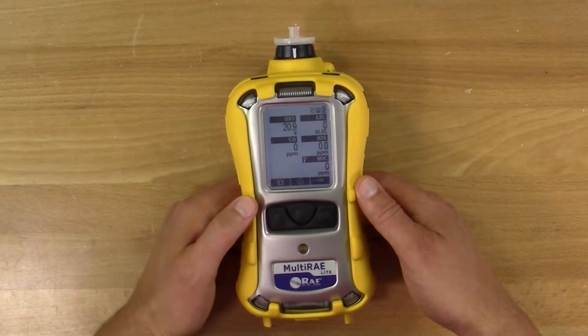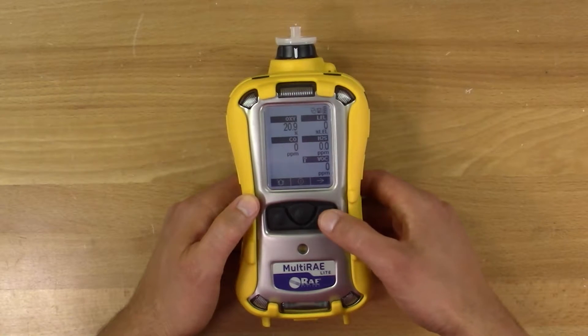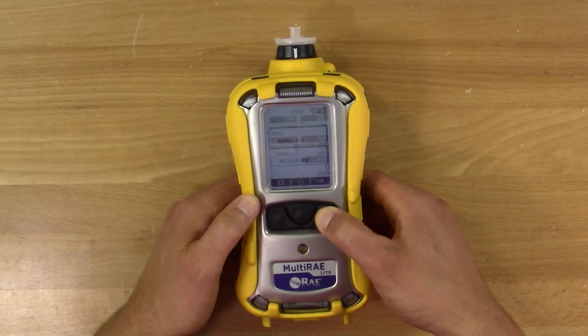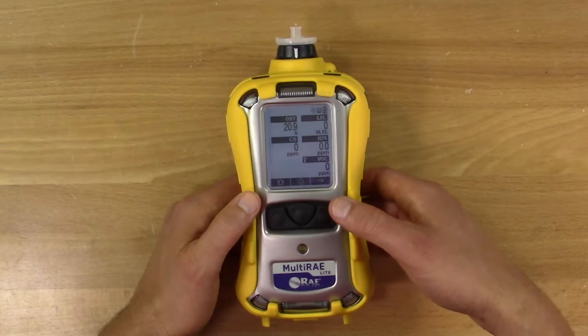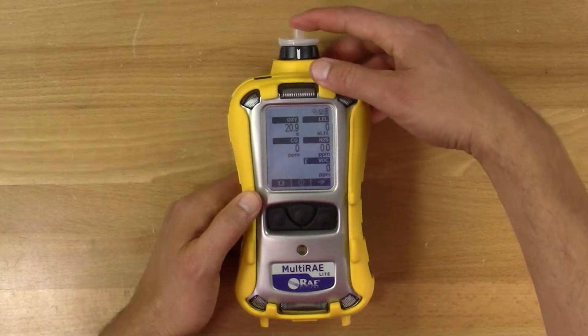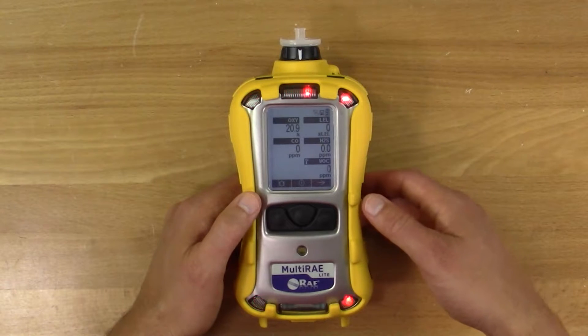Once the MultiRAE is on and the warm-up sequence is complete, check to make sure the time and date are correct so the meter displays the right calibration date. Also, check the pump is working properly by putting a finger over the inlet. If the pump stalls and the meter goes into alarm, the pump is working properly.